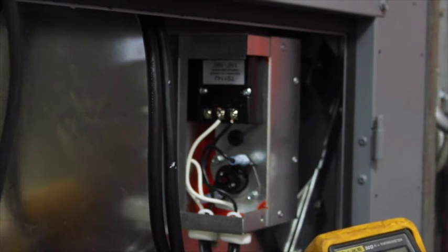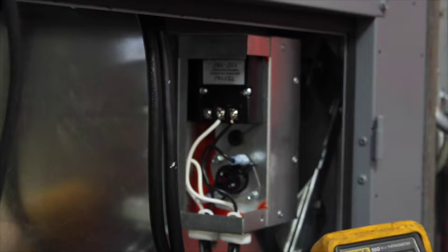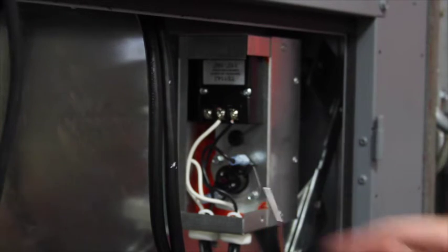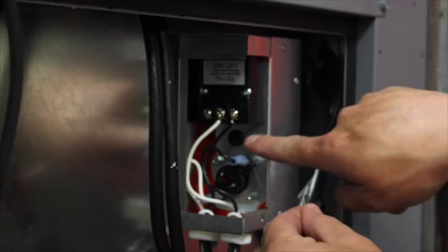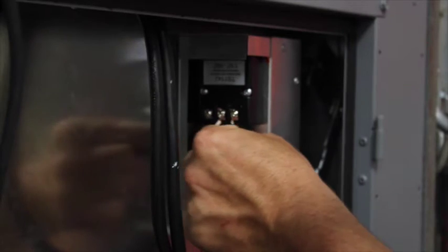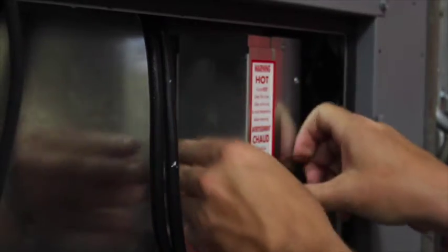Use a temperature meter and place the meter on top of the unit. There is a rubber grommet between the high limit and the discharge sensor. The grommet is in the middle, be sure to place your sensor into the grommet. Next put the wire to the side and reinstall the cover.